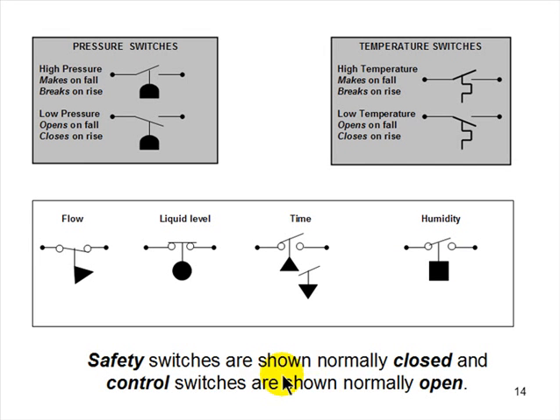Safety switches are always shown normally closed. Control switches are shown normally open. If these two switches were shown closed, that means the switch is actually on the line, then they are high pressure and low pressure switches. If they're safety switches, in other words, they'd be in series with a compressor contactor to save it. They're safety devices. This is a heating thermostat because it's a control. Its switch is shown normally open. If it was closed, it would be a high limit, probably in a furnace or something like that.